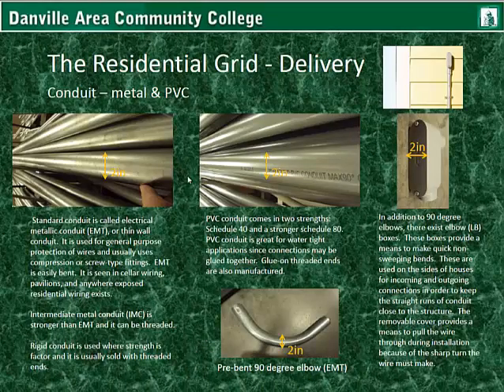So now we need to talk about conduit — it's almost like a piping that you run conductors through. The standard conduit is called Electrical Metallic Conduit, or EMT, also called Thin Wall. It is used for general purpose protection of wires, and usually uses compression or screw type fittings. EMT is also easily bent. It's seen in cellar wiring, pavilions, and anywhere exposed residential wiring exists.